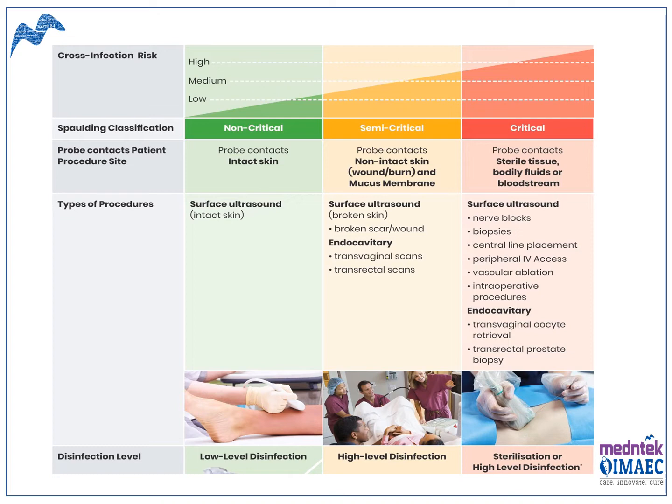Now look at semi-critical medical devices. These are probes that contact non-intact skin like wounds, burns, and mucous membranes. For example, an endoscope directly touching the blood and mucosal lining. So that will be a semi-critical medical device, but it needs high level disinfection.